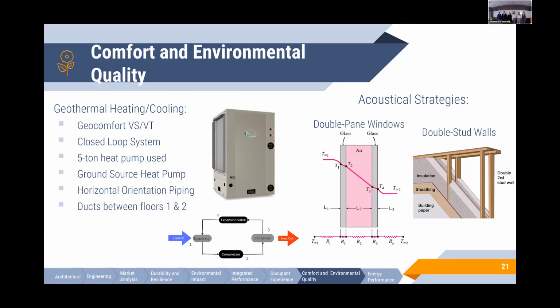For the geothermal system, we chose a GeoComfort VS/VT system. This is a closed loop system, circulating antifreeze rather than water, which needs to be drained with an open loop system. We chose a 5-ton heat pump based on the square footage of the house, using a ground source heat pump because it's more efficient in winter, less noisy, and requires less maintenance than an air source heat pump.